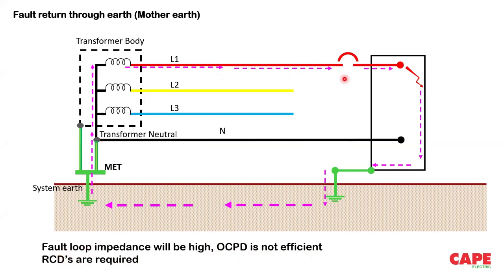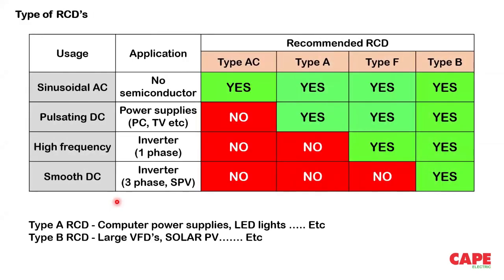So if you go for this kind of a network, which is called a TT network, fault loop impedance will be very high. Automatic disconnection by OCPD will not happen, and you require a device called an RCD, residual current device. When you select an RCD, please note that there are 4 types of RCDs. Depending upon your usage, you should select the appropriate type of RCD.